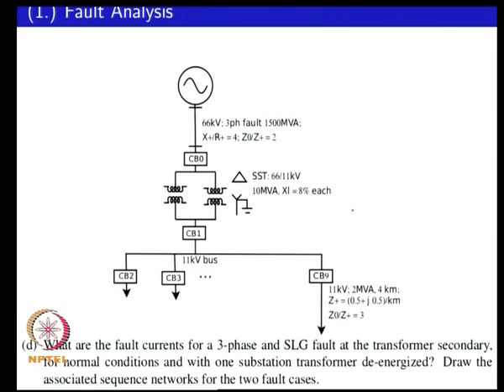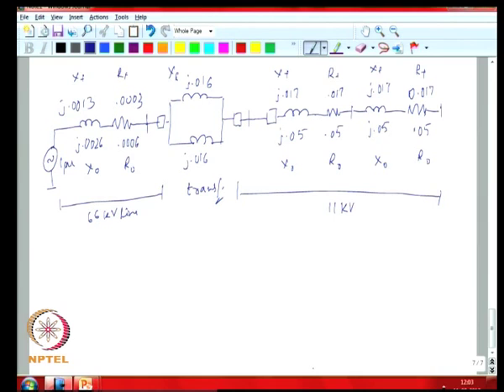The question is: what are the fault current levels for a three-phase and single line-to-ground fault at the transformer secondary for normal conditions — when both transformers are available — and when one transformer is de-energized for repairs or maintenance? Draw the associated sequence network for these two fault cases. We will look at the first case of a fault at the transformer secondary when only one transformer is present.